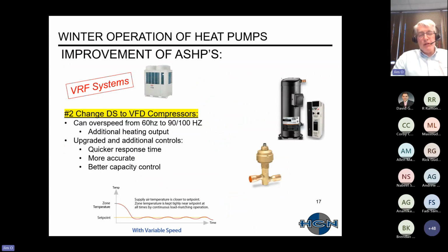Next, stealing sort of from the VRF world, they're changing on-off or digital scroll compressors to VFD compressors. If you have a VFD compressor, you're able to overspeed it from 60 hertz up to 90 to 100 hertz. This will produce additional heating output. And inherent with VFD compressors versus the old mechanical ones, you'll have quicker response times and more accurate capacity control, as shown on that graph there. And then, just lapping on the right there, there's a compressor with its VFD next to it.